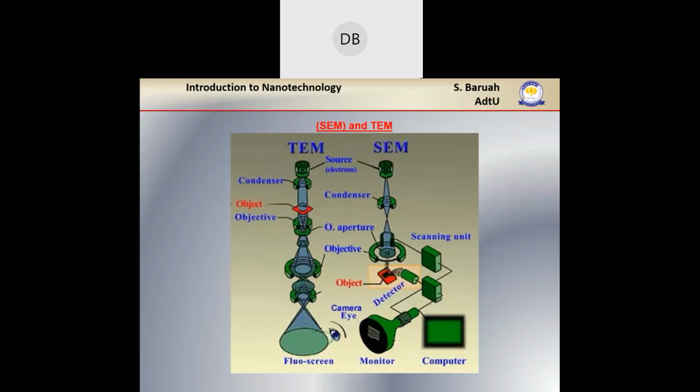Then the electrons acquire enough energy from thermal energy that takes them to a very, very excited level, so that they can even overshoot the work function and leave the material. So basically we have some filaments here, mostly tungsten, but it can be some other ones also. We heat them up and we have enough free electrons near the filament. That means the filament is throwing out free electrons.